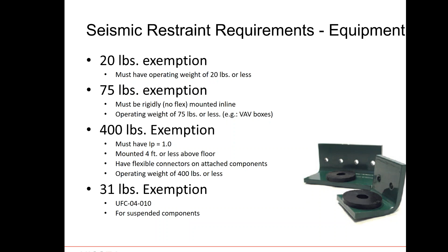And then usually for ground-mounted, floor-mounted equipment, there's a 400-pound rule, but it has a few different factors. This is only for Ip of 1.0. They have to be mounted 4 feet or less above the floor, so usually they're connected down to the ground. They have to have flex connectors on the attached components, and obviously have an operating weight of less than 400 pounds. Now, for a different code, the UFC, there's the 31-pound exception, which basically says anything that's under 31 pounds is exempt.